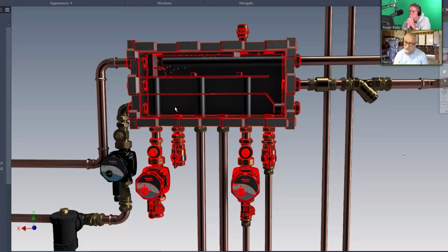But because sealed systems and, let's say, complete boilers coming from the manufacturer came on the market, installers forgot the basics and they just rely on the mechanical boiler to do all the thinking, if you know what I mean. Whereas if you go back to basics, you have to figure out where's the neutral point, how much water you're pumping, what size pipe you're using, how quickly the water is moving, and then whether you're letting the water stay in the boiler long enough to pick up heat, or whether it's so slow going through the boiler that the boiler is overheating.